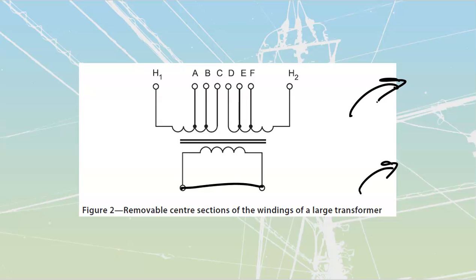The other thing this allows for, which the book doesn't really talk about much, is the physics of a fault current. What happens during a large fault current? We get massive amounts of magnetic force as well as massive amounts of thermal force, meaning heat expansion. By cutting this out in the center, we allow a shorter section of winding to move and expand towards the center, as well as a larger section over here.